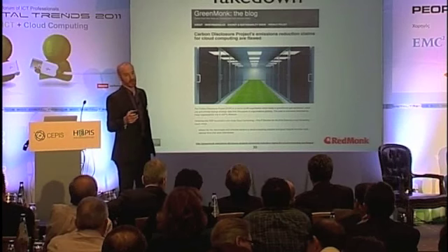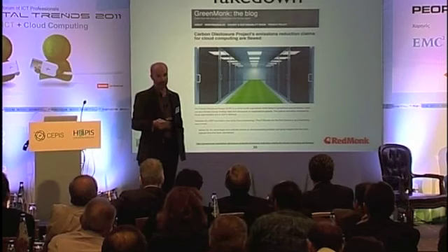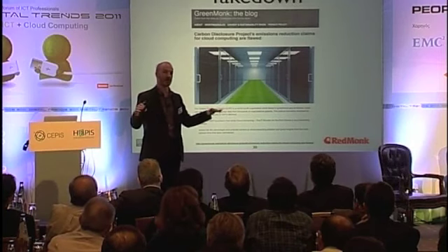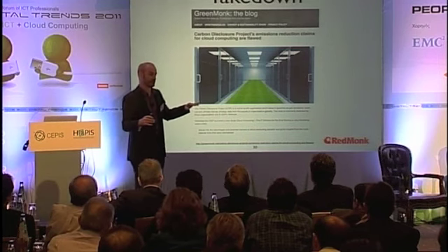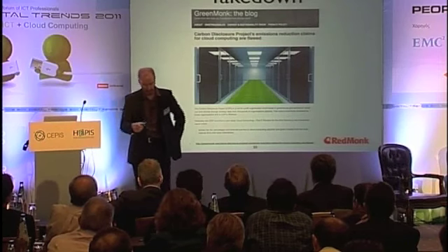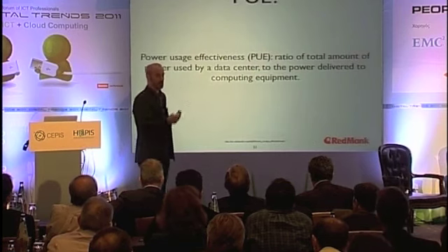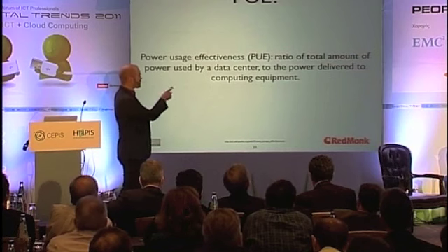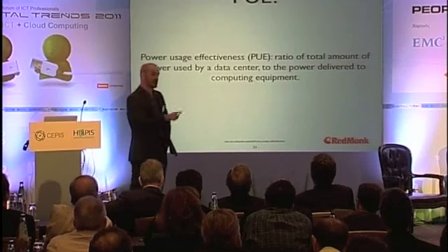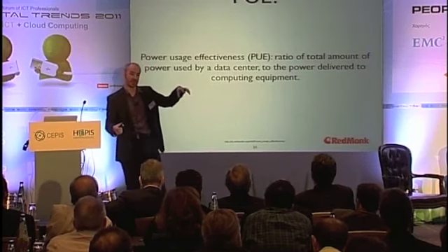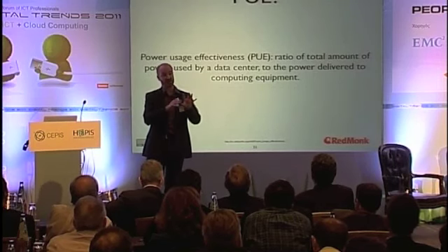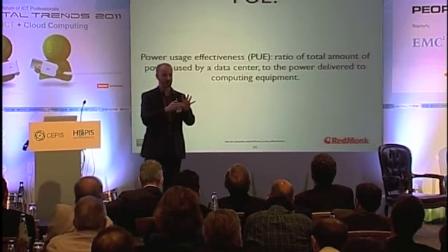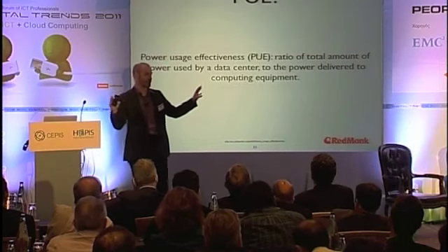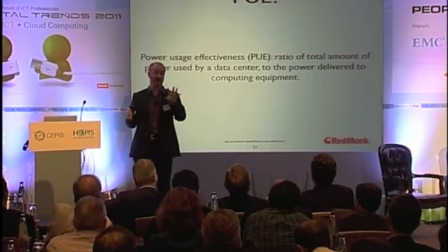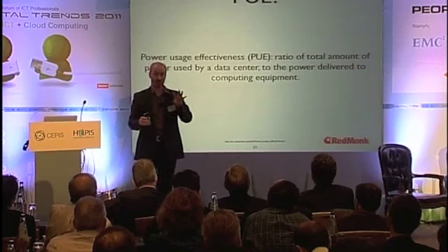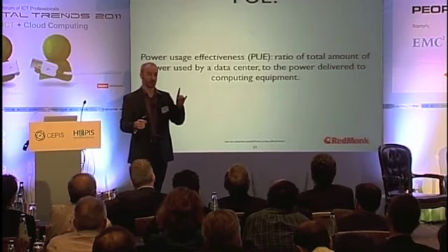They based their model on this PUE metric, which is a widely used metric, but they've based it on an average PUE across the entire United States, which is put out by the EPA. So that's not really very indicative, firstly. But secondly, PUE is a ratio of the total amount of power used by a data center compared to the power delivered to the computer equipment. The total power delivered to a data center is the power delivered literally to the door of the data center, which goes to power the lighting, the cooling, the UPSs, the whole thing. And it's a ratio of that to the amount of power which actually makes it to the IT equipment. So the closer your PUE figure is to 1.0, the better.